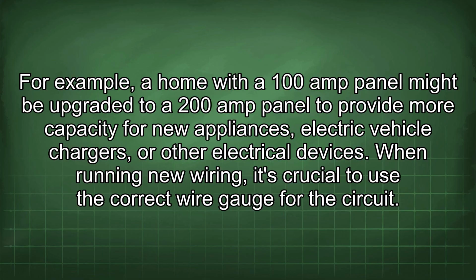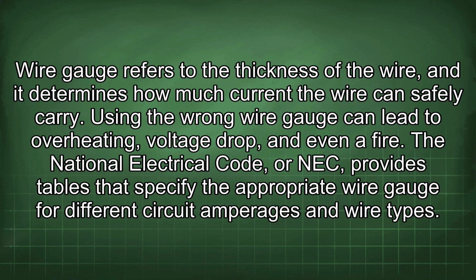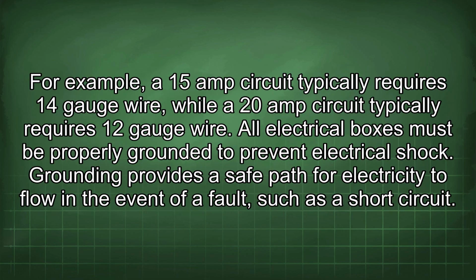When running new wiring, it's crucial to use the correct wire gauge for the circuit. Wire gauge refers to the thickness of the wire, and it determines how much current the wire can safely carry. Using the wrong wire gauge can lead to overheating, voltage drop, and even a fire. The National Electrical Code, or NEC, provides tables that specify the appropriate wire gauge for different circuit amperages and wire types. For example, a 15-amp circuit typically requires 14-gauge wire, while a 20-amp circuit typically requires 12-gauge wire.